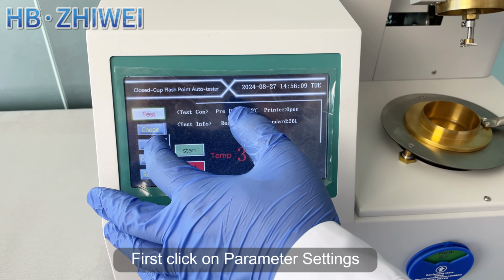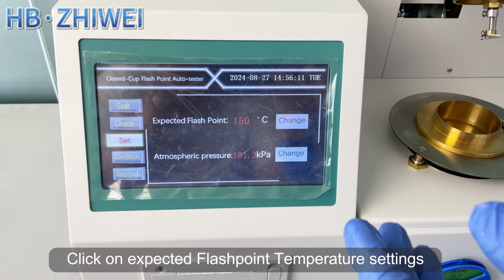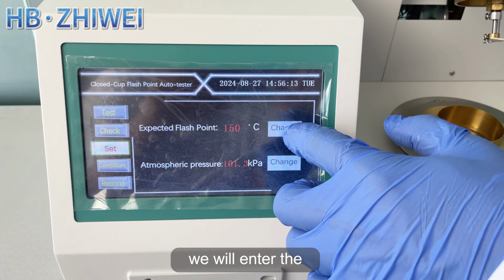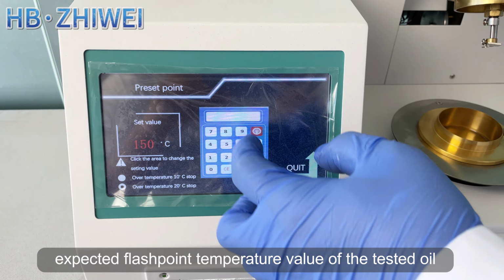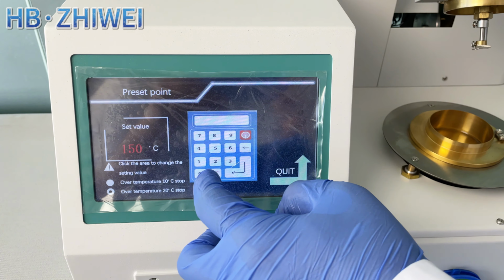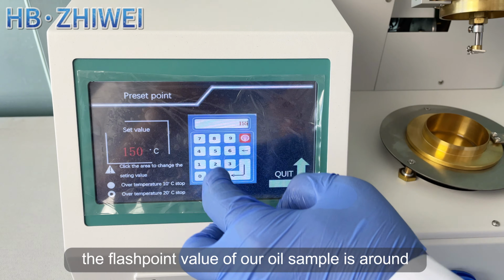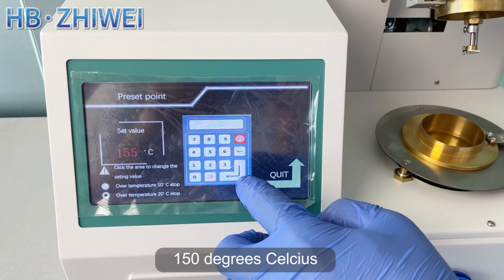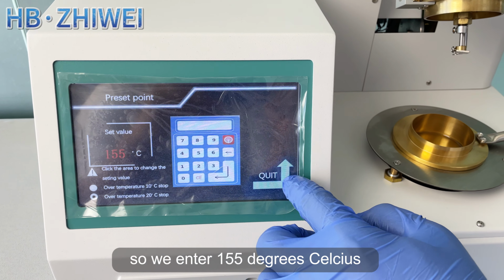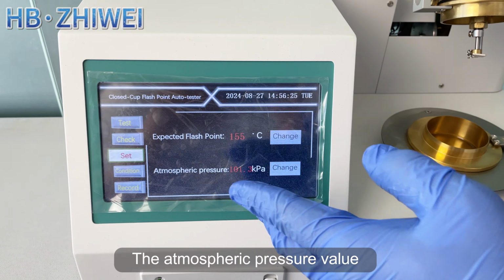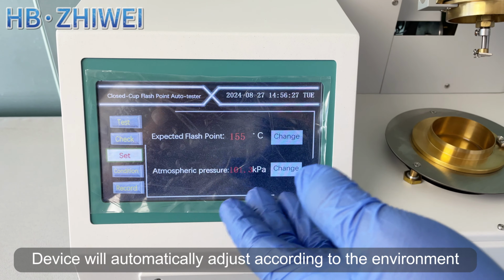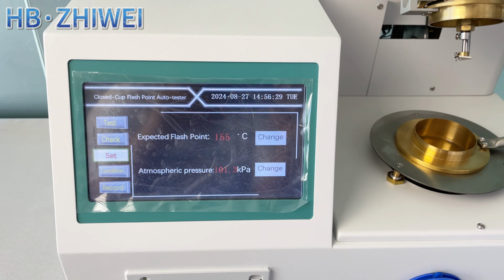First, click on Parameter Settings. Click on Expected Flashpoint Temperature Settings. We will enter the expected flashpoint temperature value of the tested oil. The flashpoint value of our oil sample is around 150 degrees Celsius, so we enter 155 degrees Celsius. The atmospheric pressure value device will automatically adjust according to the environment.